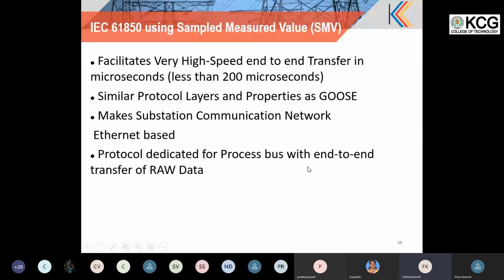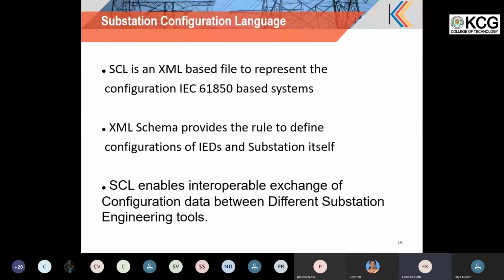Then moving on to substation configuration language. One of the key advantages, as I mentioned, for 61850 is configuration. It represents the configuration in XML format. So an XML based schema is used to represent the complete communication parameters plus all the data model, logical nodes, everything, and a schema is defined for the same. This XML format is known as substation configuration language, in short SCL.